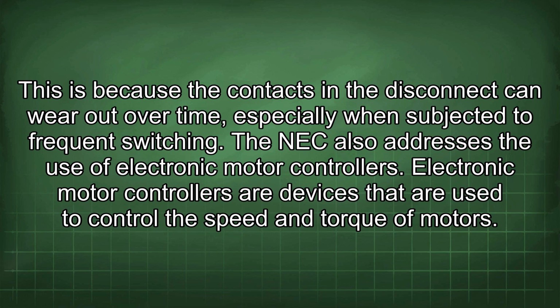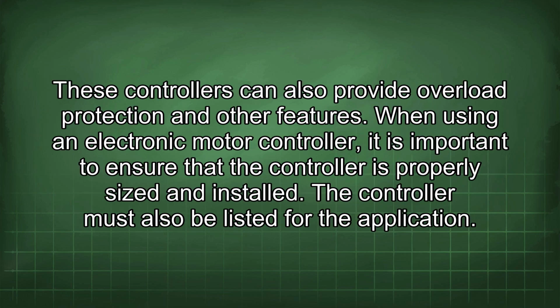The NEC also addresses the use of electronic motor controllers. Electronic motor controllers are devices that are used to control the speed and torque of motors. These controllers can also provide overload protection and other features. When using an electronic motor controller, it is important to ensure that the controller is properly sized and installed. The controller must also be listed for the application.